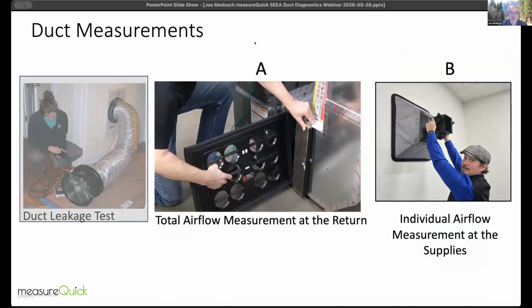So NCI and other folks are promoting that I could use my TrueFlow grid to actually get a total measurement out of this. So that's the greatest thing about that. And there is no greater tool on the market right now that assesses static pressures, which most people are not measuring either, and airflow all in one quick step. Usually if you took 10 minutes to do this test, it was probably because it was your first time doing it.